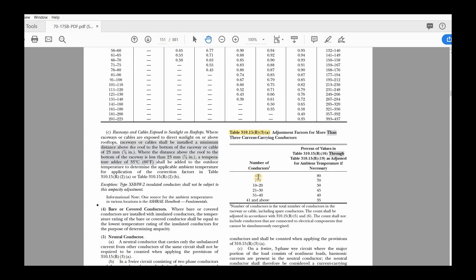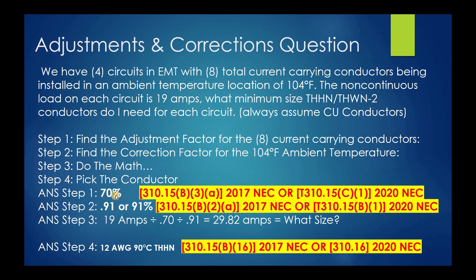We have eight current-carrying conductors, so we come down to the seven-to-nine range in that table, and that gives us 70%. Convert that to a decimal by moving two places left: 0.70. That 70% value comes from Table 310.15(B)(3)(a) in the 2017 code. In the 2020 code, that changes to Table 310.15(C)(1) — just a heads up, it flows much better in the 2020 code, but it still works the same way.